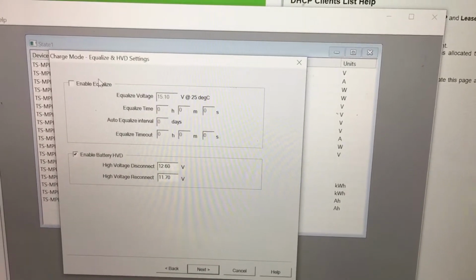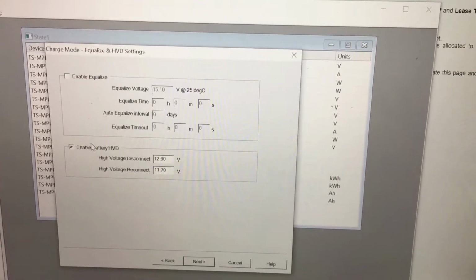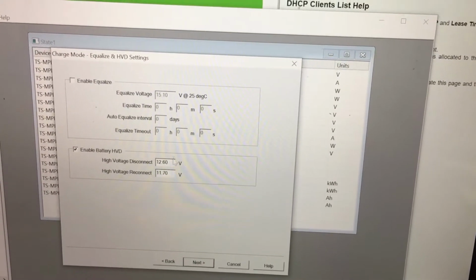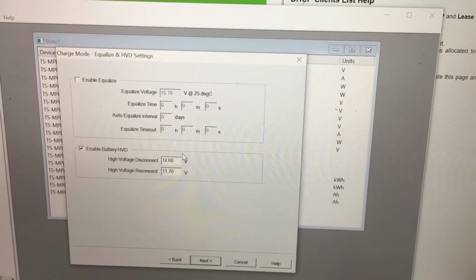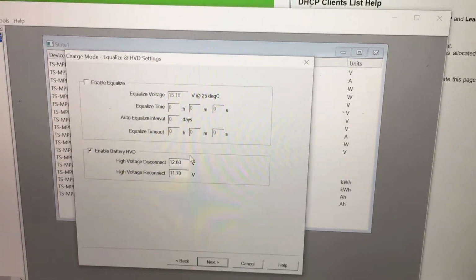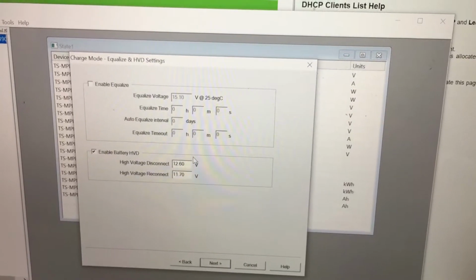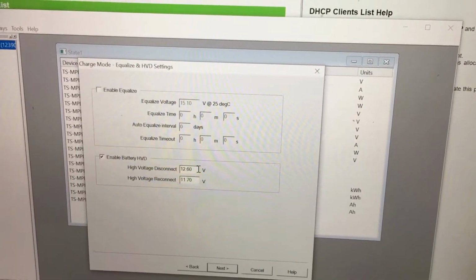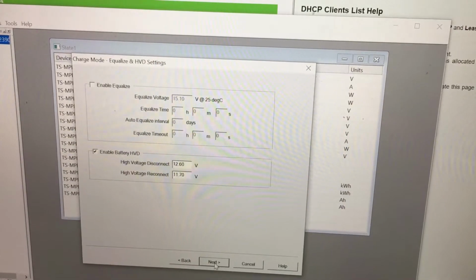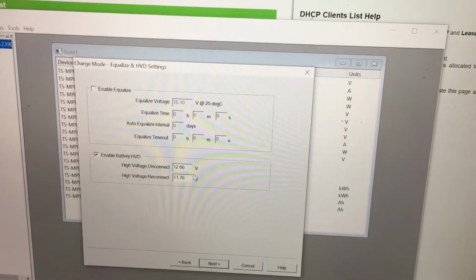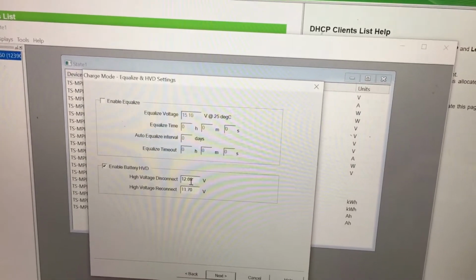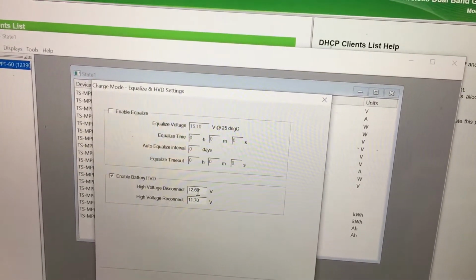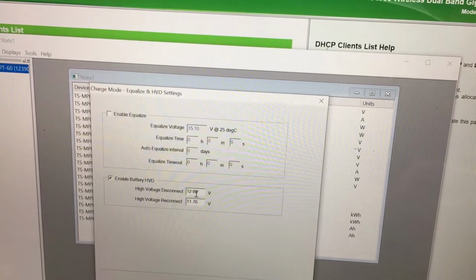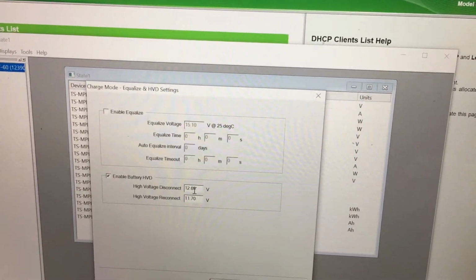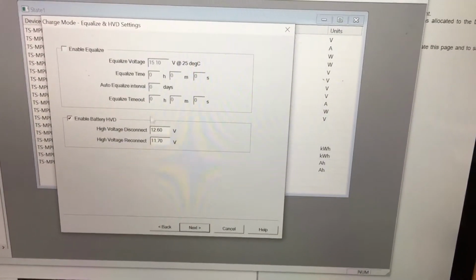I shut off the equalize, and here I have the high voltage disconnect, which I spoke of earlier. This is set so that if something went crazy with the battery charger and something catastrophic happened, it would disconnect at 4.20 volts per cell. If you take 12.60 and multiply by 2, that's 25.2, divided by 3, divided by 2, ultimately gets you to 4.2. That's why I have that set there.